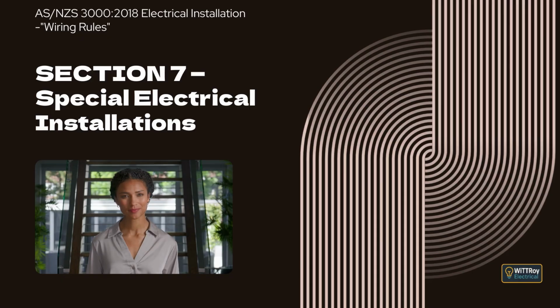This clause explains that where emergency equipment is required by building codes, switchboards supplying that equipment must be constructed so that emergency switchgear is separated from other switchgear by metal partitions to limit the spread of faults. Clause 7.2.10 Emergency motor room less lifts. This clause introduces additional requirements for emergency motor room less lifts, also known as MRL lifts.